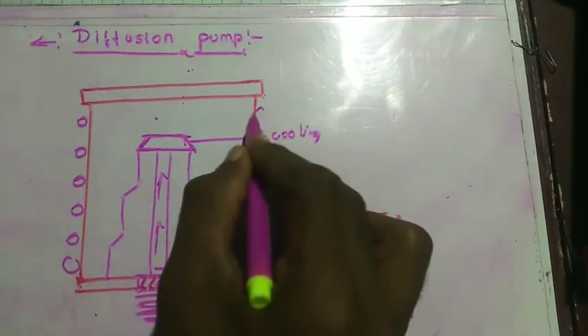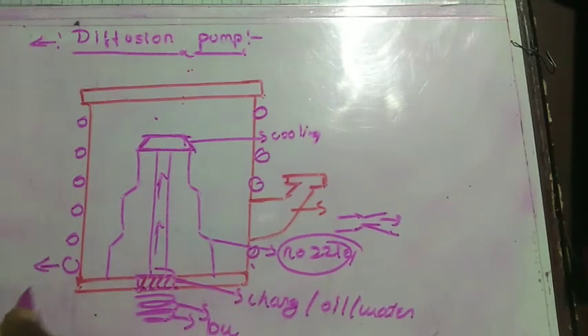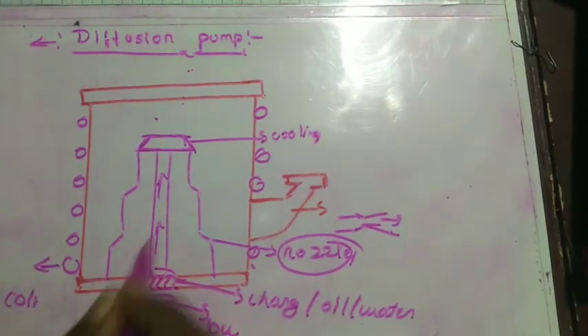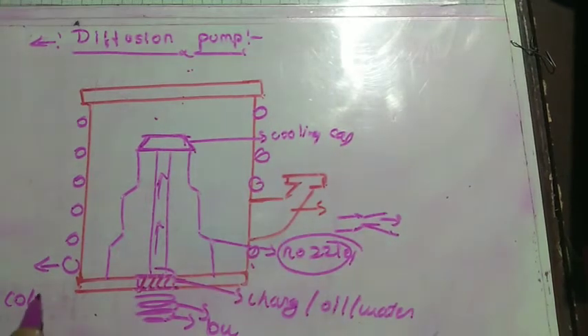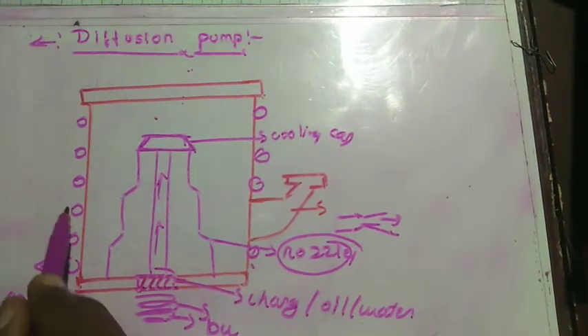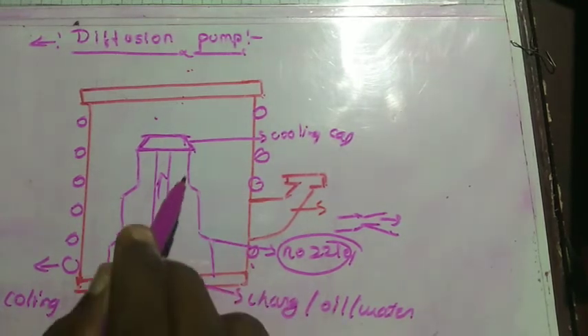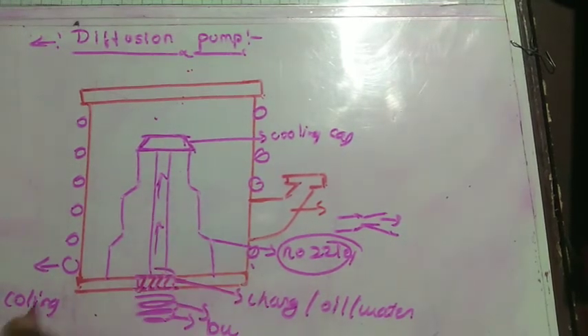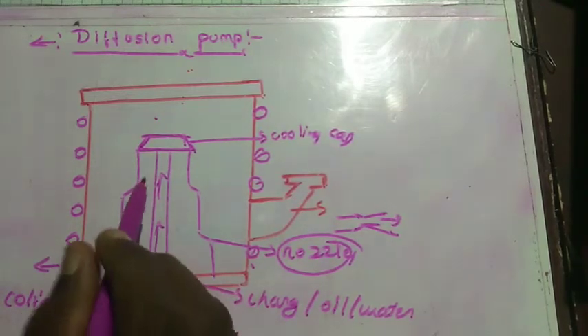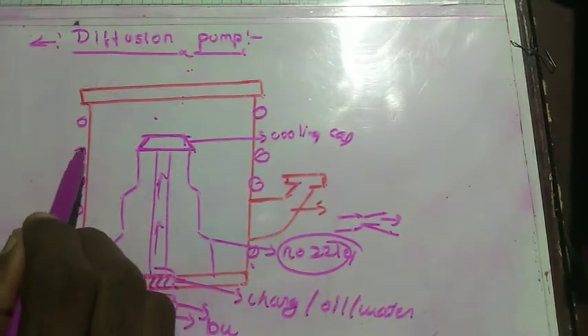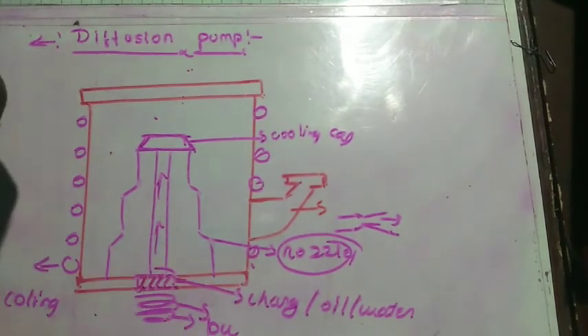This is the lower part of the diffusion pump. These are called the cooling coils, and their working is similar to the cooling cap. These are circular coils present in the outer frame of the diffusion pump that help to cool the system by sucking the heat out from the system.